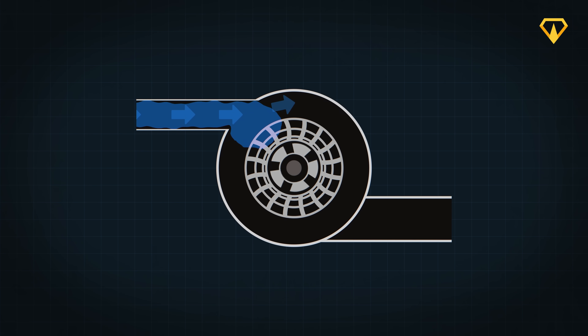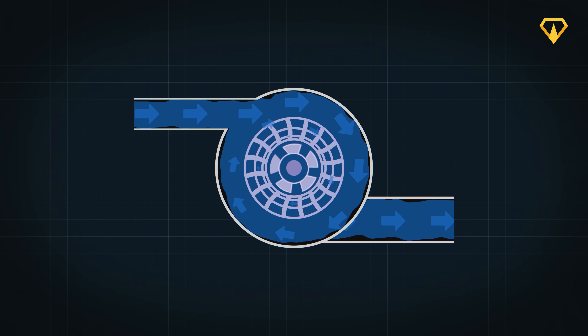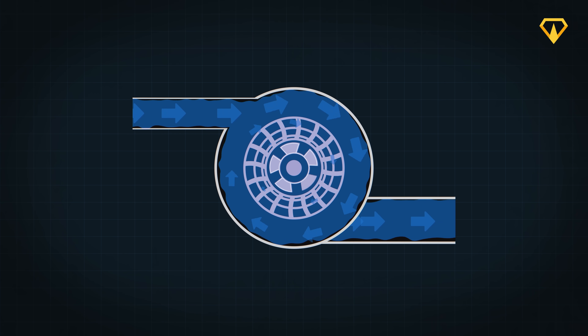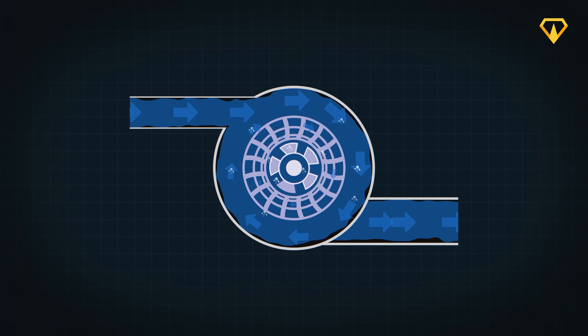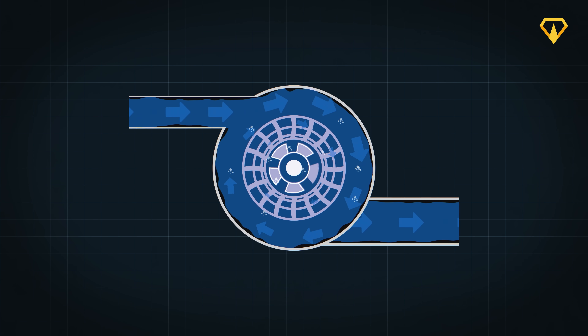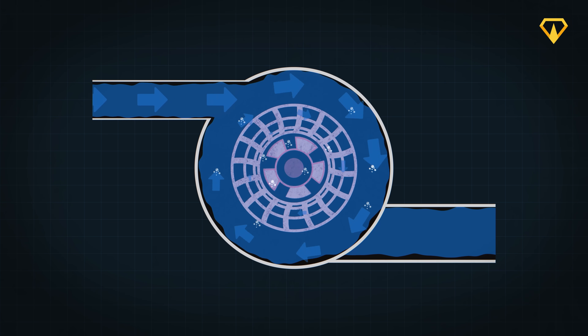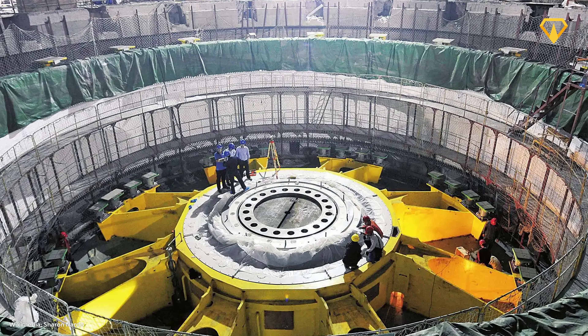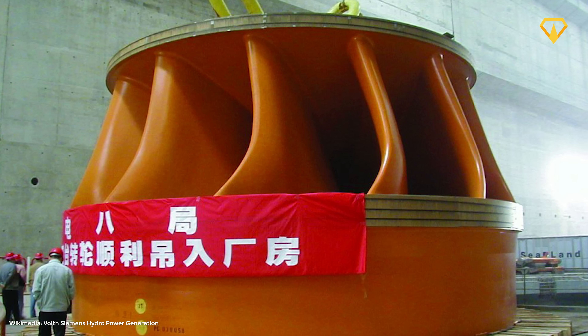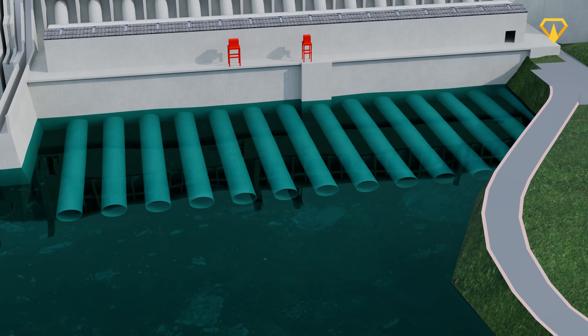But despite all of this, engineers encountered a problem. During the first test, the prototypes of the turbines vibrated and nearly shook themselves to pieces. This disrupted the flow of water through the runner and guide vanes, which caused tiny pockets of water vapor — known as cavitation bubbles — to appear on the metal surfaces of the vanes. These bubbles aren't harmless: they can eat away at the stainless steel components, causing great damage to the turbines. So engineers were forced to keep going back to the drawing board, until they eventually succeeded in designing turbines that can channel over 900 tons of water per second without tearing themselves apart.